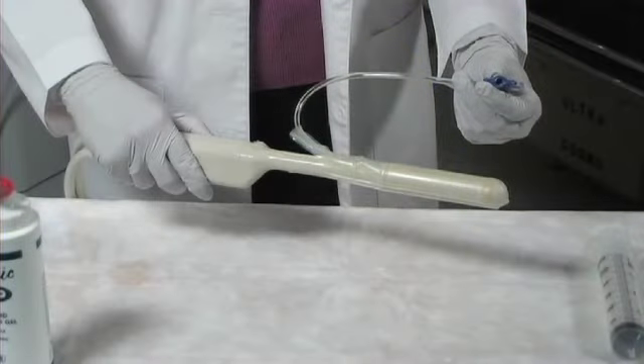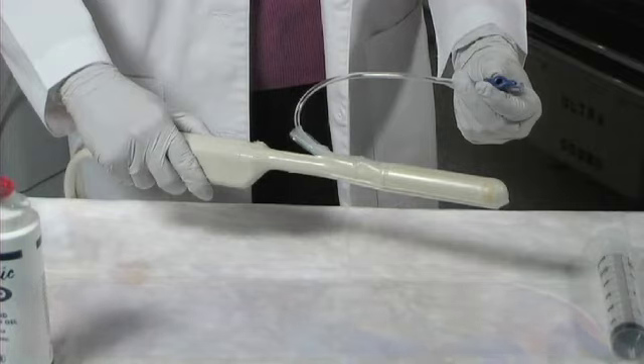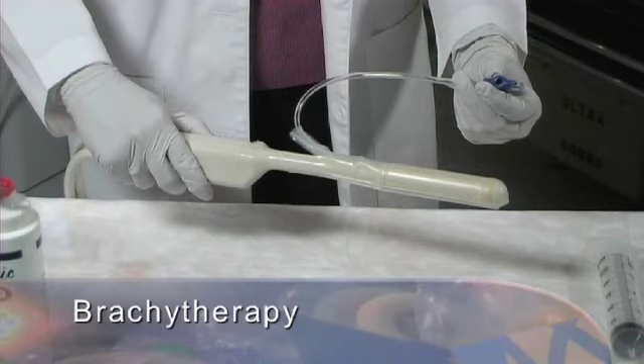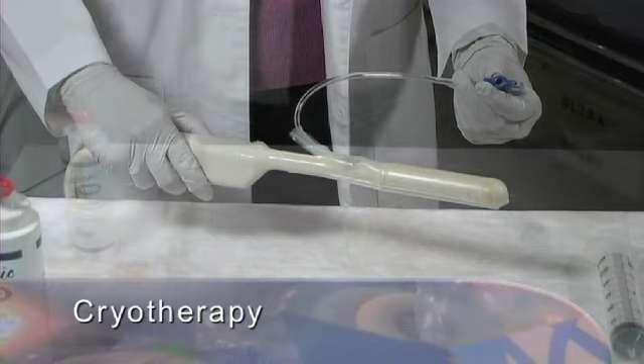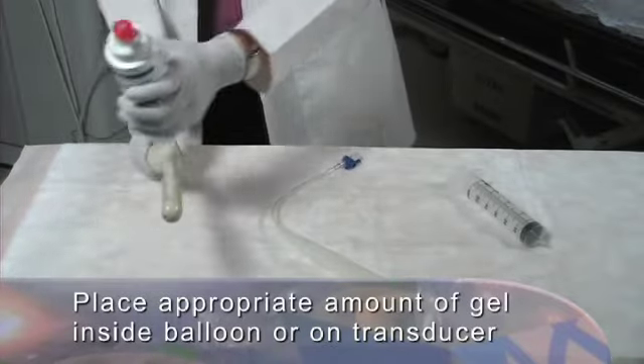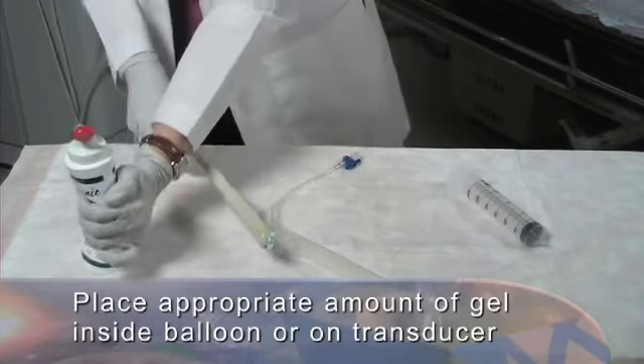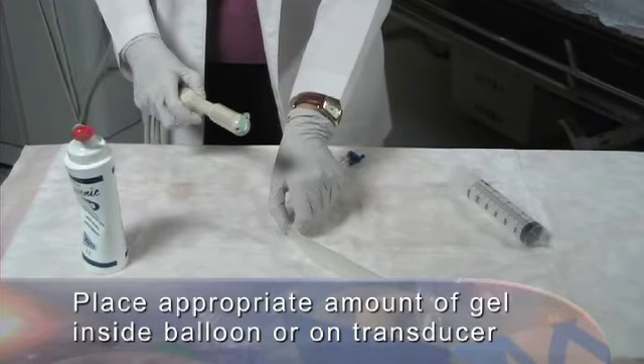An alternative covering method for transrectal procedures may involve use of an endocavitary balloon. This transducer standoff device is an alternative example of how to perform scanning and transperineal procedures for needle guidance, core biopsy, fiducial marker placement, brachytherapy, or cryotherapy. Placing the appropriate amount of gel inside the endocavity balloon or on the transducer face aids in scan quality, application, and removal of the balloon.